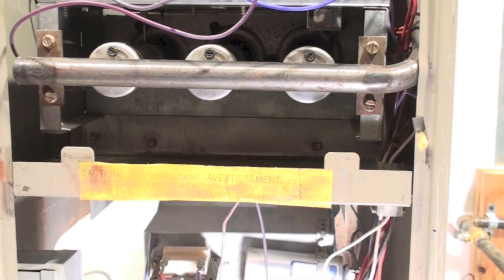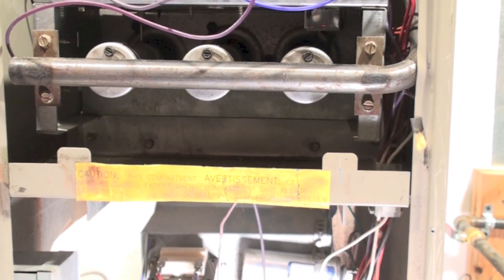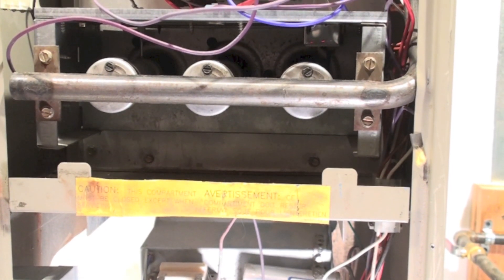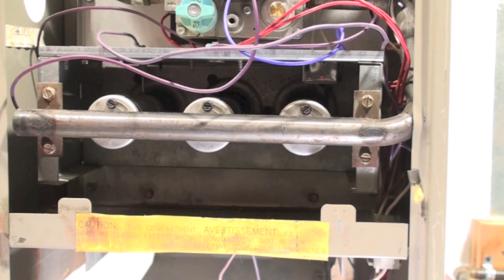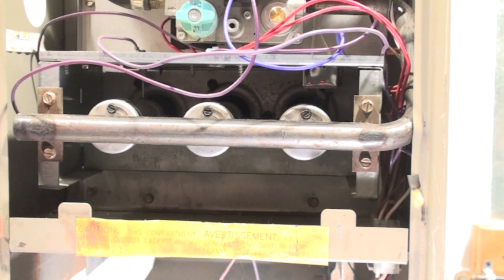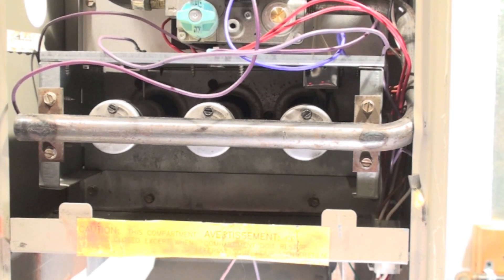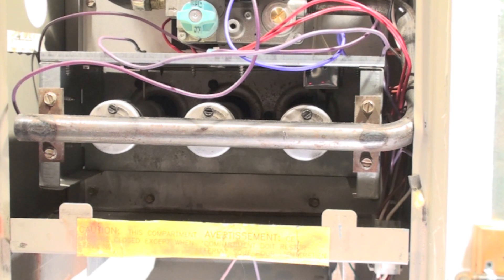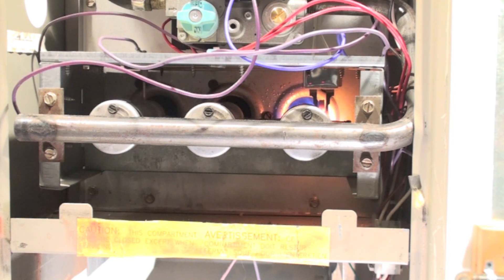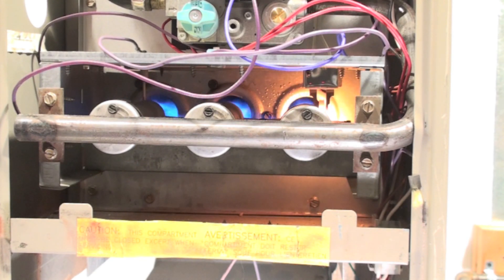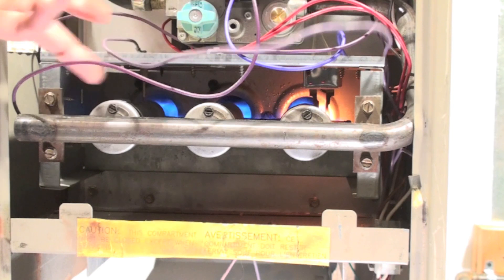Inducers on. Up here kind of looking at the burners. Okay, hot surface igniter should be coming on in a minute. Here it's coming on. Okay, we proved flame because our flame rod was hooked up.